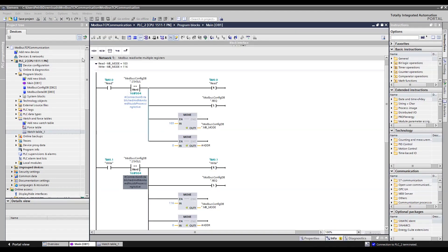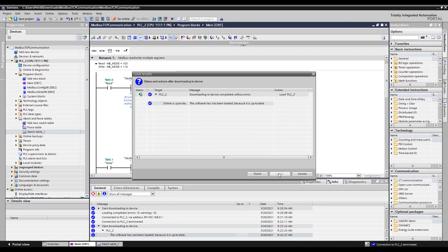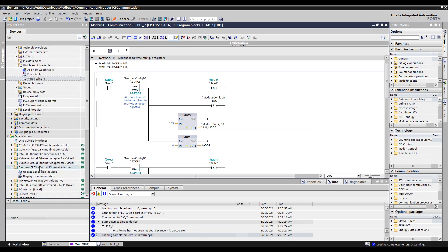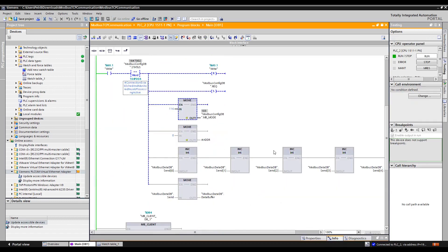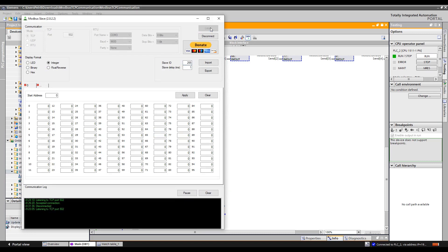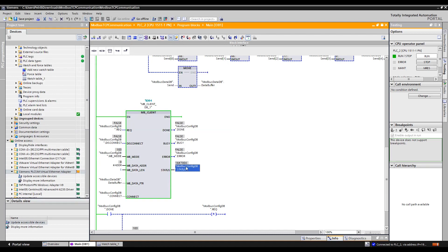Now download the project. If asked which interface to use, select the Siemens PLC SIM Virtual Ethernet Adapter. Once online, check the Modbus function block. The correct status is 7004, meaning it's ready for transfer. Open Modbus Slave, click Listen, and within a second you should see an incoming connection accepted. Status returns to 7004 — ready for transfer.